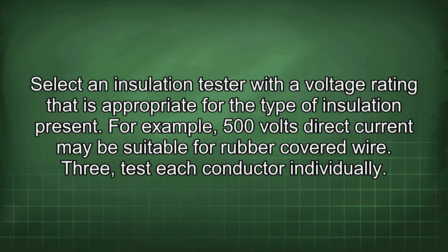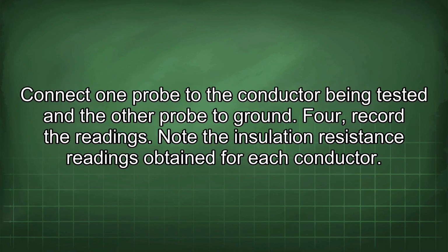3. Test each conductor individually. Connect one probe to the conductor being tested and the other probe to ground. 4. Record the readings. Note the insulation resistance readings obtained for each conductor.